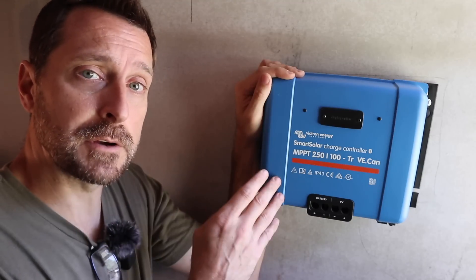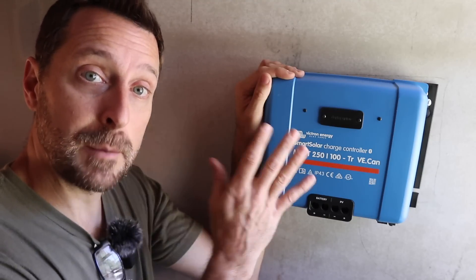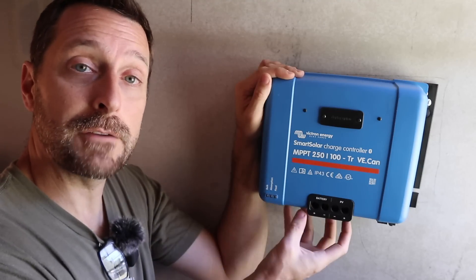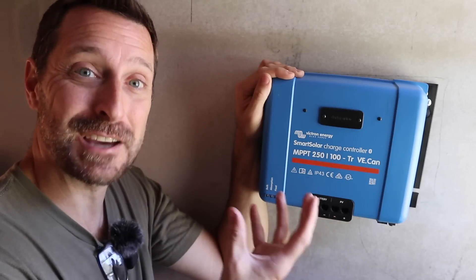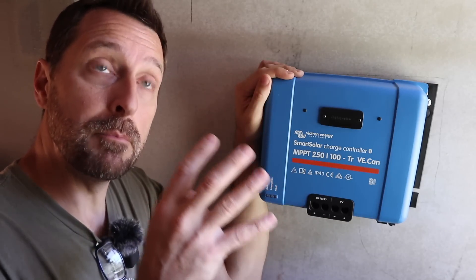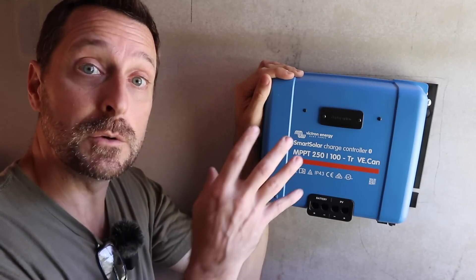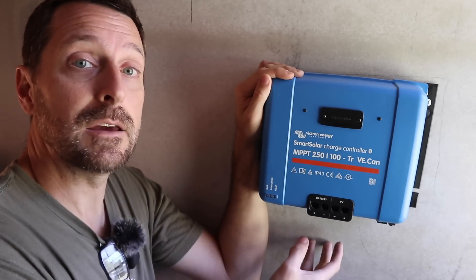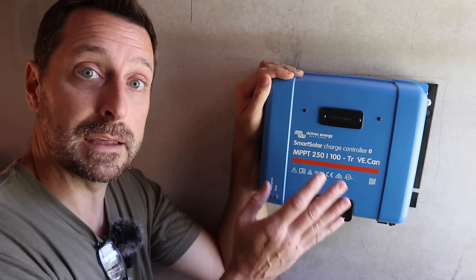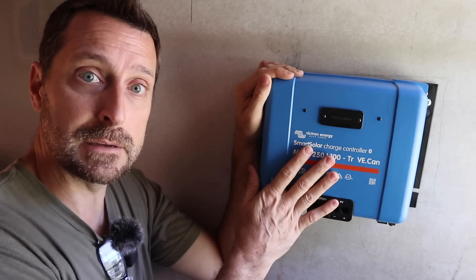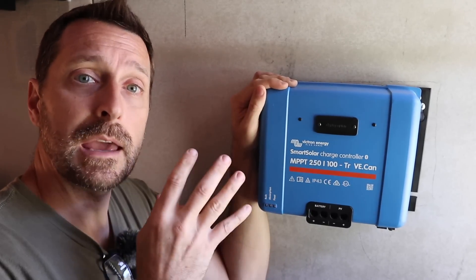Now, here's another challenge with the Victron system, is that the MPPTs do not have anywhere on the MPPT itself to connect conduit. So maybe it's just running conduit through most of the building until you get to this point. And then right here, cutting it off the conduit and just running the wires out the end into the MPPT. And that's what I've seen done in a few cases.